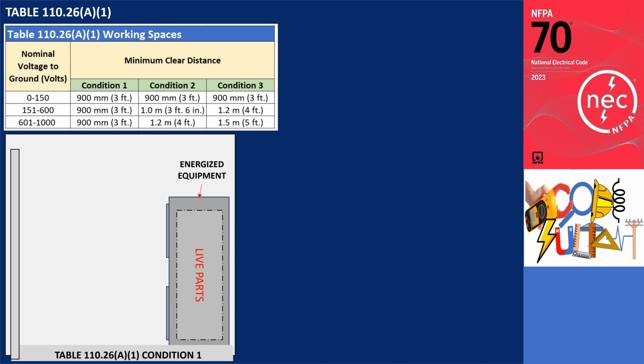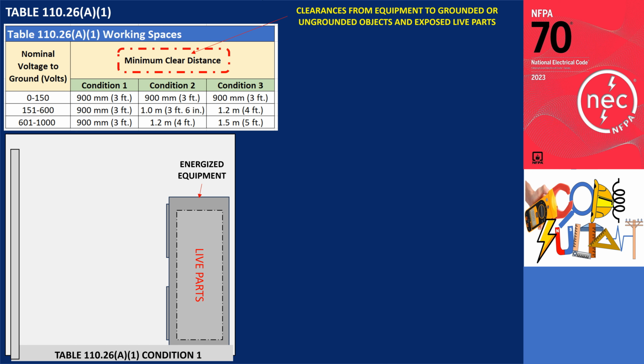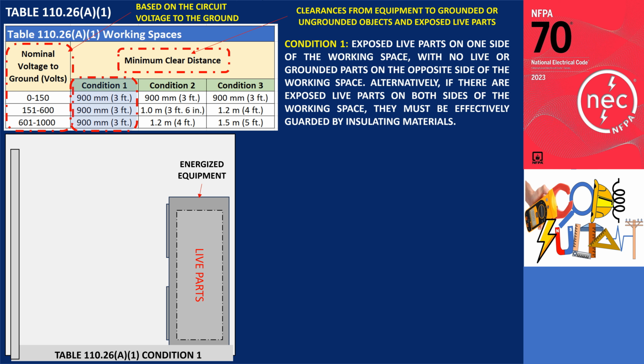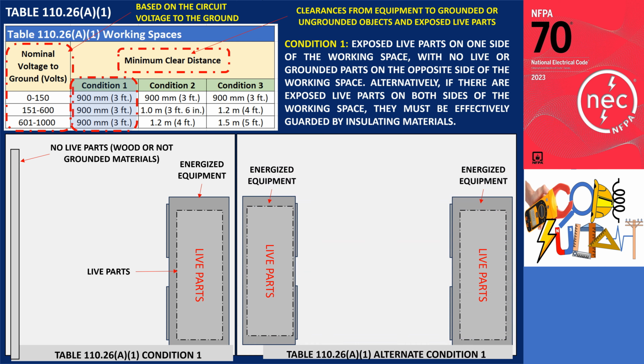Table 110.26(A)(1) provides requirements for clearances from equipment to grounded or ungrounded objects and exposed live parts based on the circuit voltage to the ground. An example is illustrated that exemplifies compliance with Condition 1, where the exposed live parts are located on one side of the working space, and there are no live or grounded parts present on the other side of the working space. Alternatively, Condition 1 is also met when there are exposed live parts on both sides of the working space that are effectively safeguarded by insulating materials.